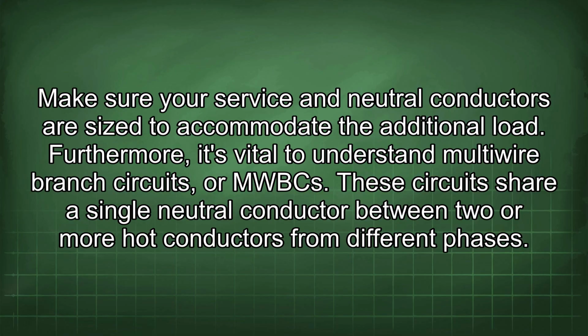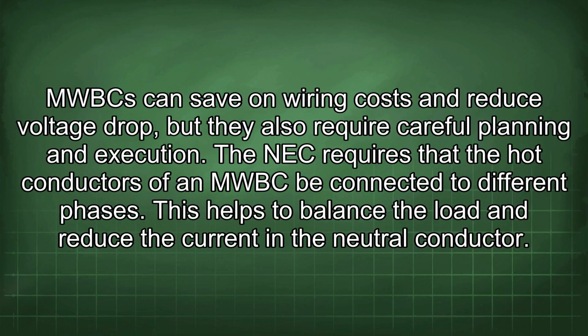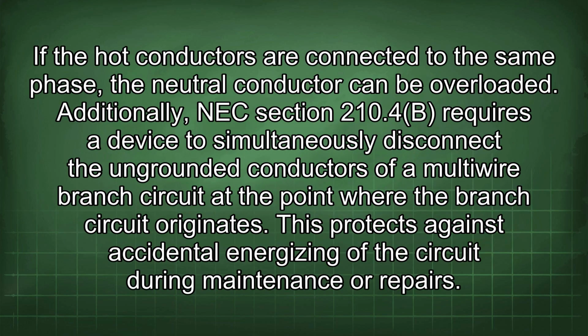Furthermore, it's vital to understand multi-wire branch circuits, or MWBCs. These circuits share a single neutral conductor between two or more hot conductors from different phases. MWBCs can save on wiring costs and reduce voltage drop, but they also require careful planning and execution. The NEC requires that the hot conductors of an MWBC be connected to different phases. This helps to balance the load and reduce the current in the neutral conductor. If the hot conductors are connected to the same phase, the neutral conductor can be overloaded.